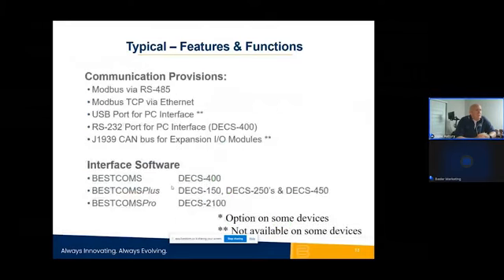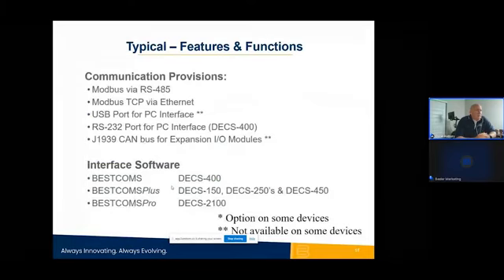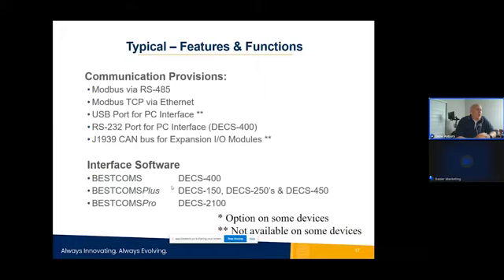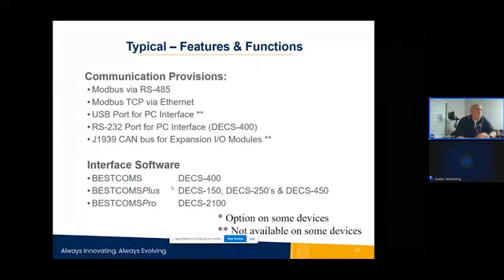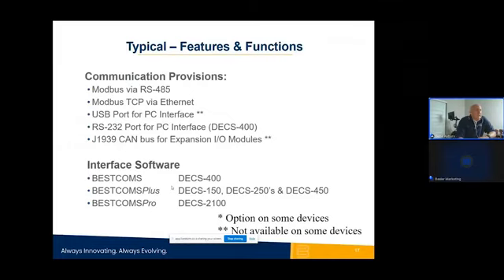Communications, you've got a lot of different options. Modbus, either through RS-485 or TCP/IP. Most of these controllers are interfaced with USB ports for the PC interface to use our BESTCOMS Plus. There are 232 ports, and then some CAN bus for expansion IO modules if you need more IO in your application, then you can use that.